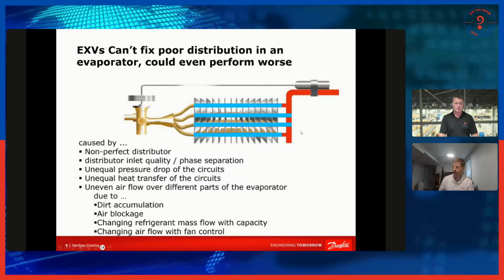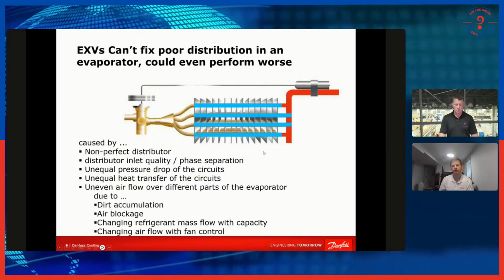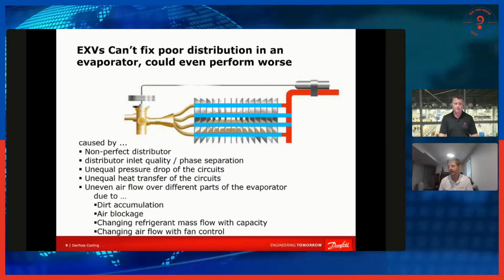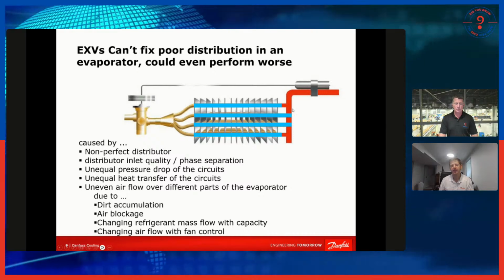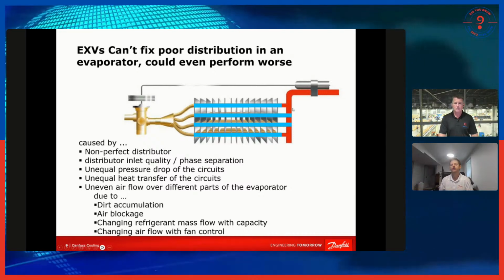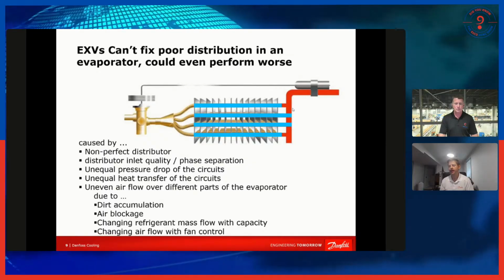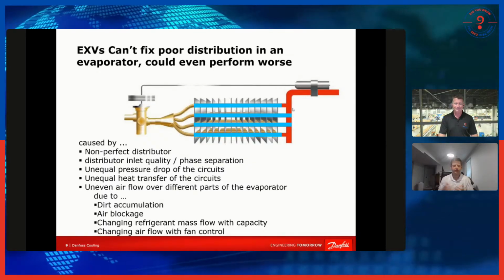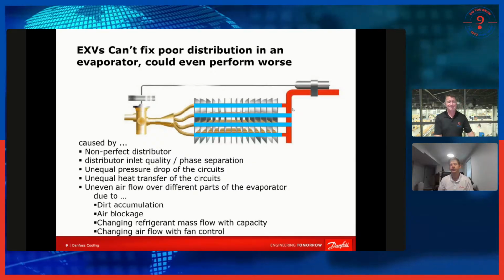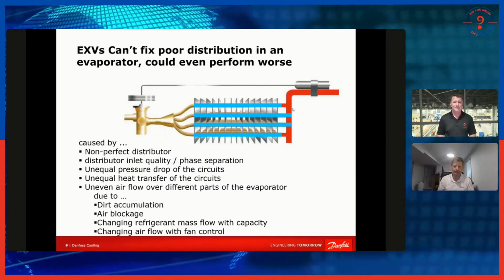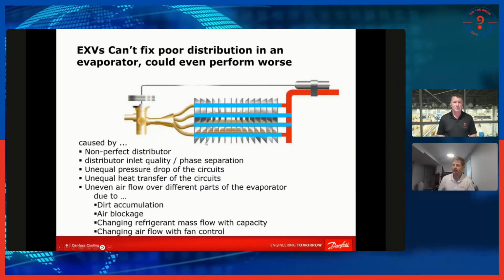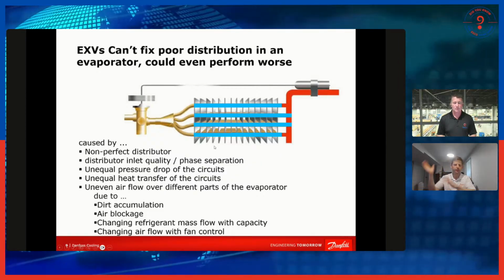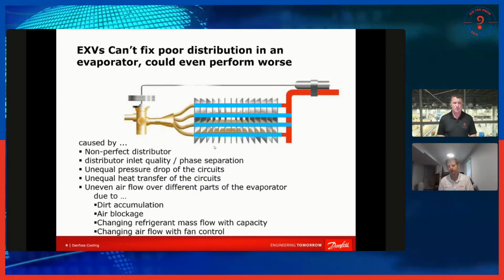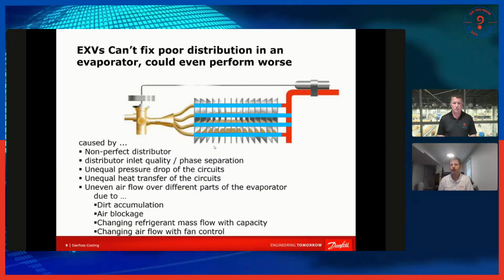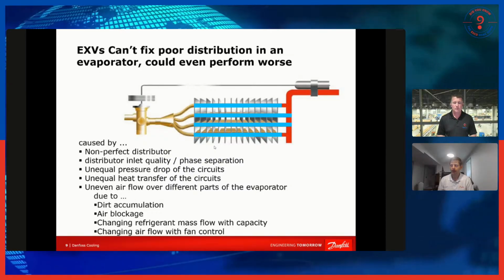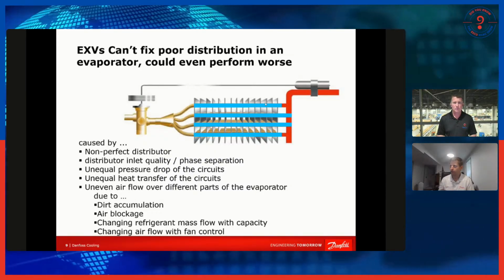This example of what I'm showing here is showing two circuits at a pretty good level. This refrigerant's boiling off just before you get to the exit, but there are two other circuits where you've got liquid coming into your suction header. And when that happens, that generally leads to a hunt. And this is going to be a problem whether you've got a TXV or EXV. Generally, with the distributor, if you can't get that design perfect, you can't get that airflow perfect, because of the shape of the coil, the way the fans bring in air, you're not always able to get perfect distribution.